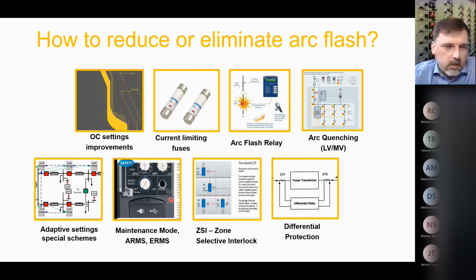Maintenance mode, so ARMS, depends how you call it. It's arc flash reduction maintenance switch or energy reduction maintenance switch. It's mainly the function of low voltage breakers, ACB breakers, and especially the trip unit of the breaker, not the breaker itself. And we'll talk about it. I will show you an example.